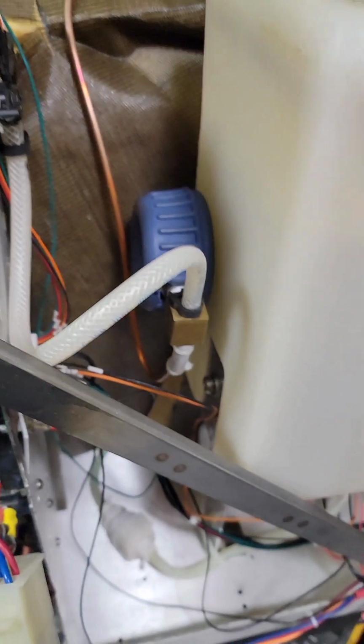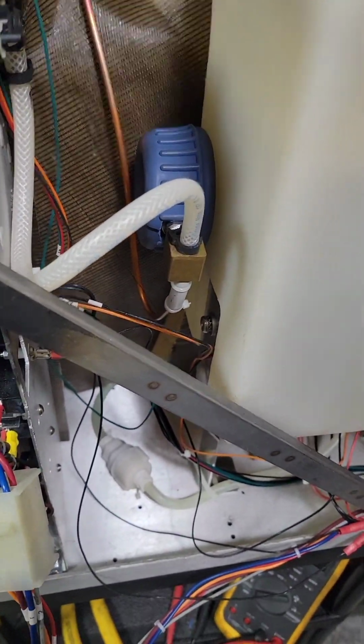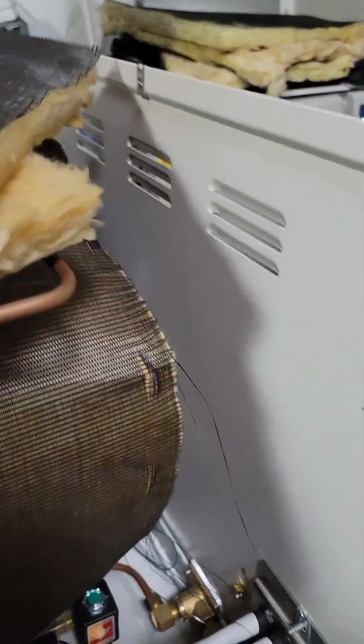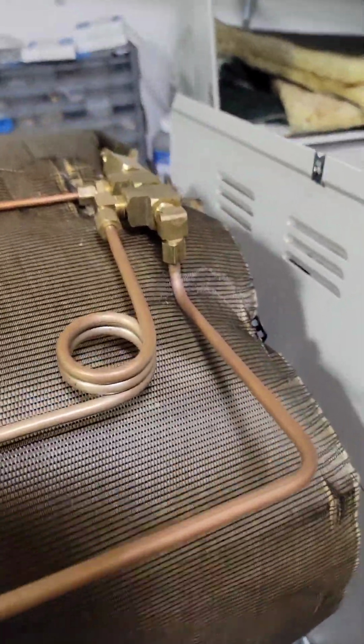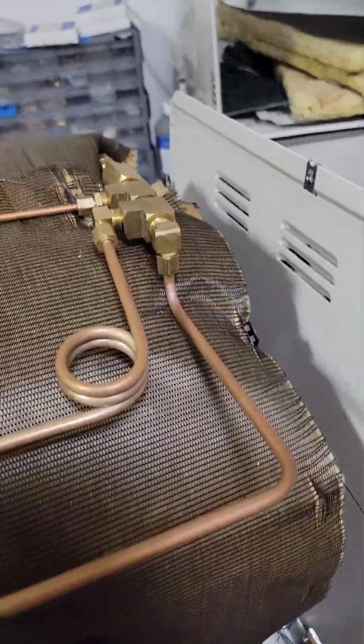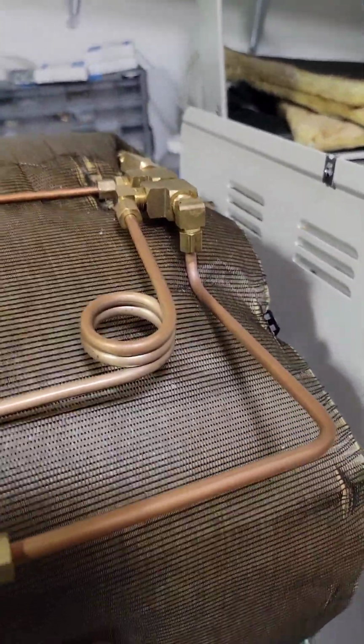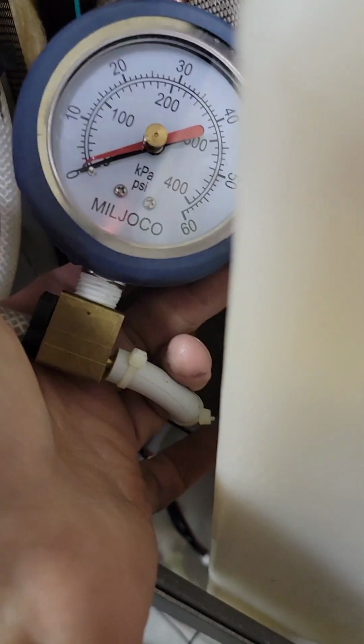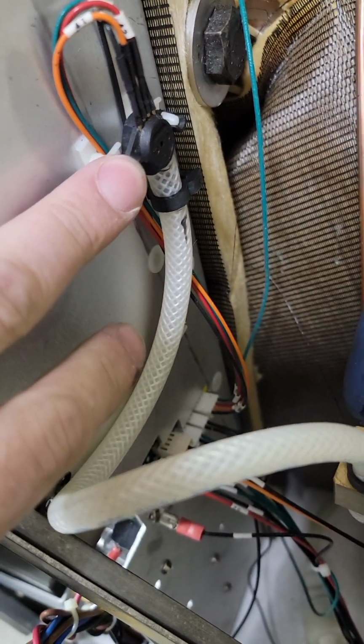If you're using the automatic unit, you really don't need to pipe in with the gauge you get provided in the Tuttnauer kit up here. It's annoying, and it's just 2 more points that could leak. So I take the Midmark gauge, that way you don't have to travel with multiple gauges, and just tee in. Same pressure sensor Midmark has, just this one is plugged in versus being soldered to a board. So I just tee in, there you go.